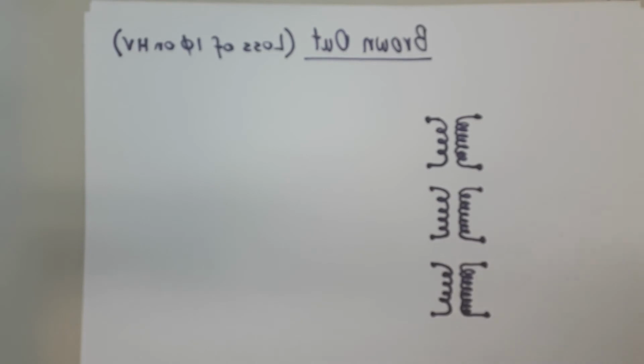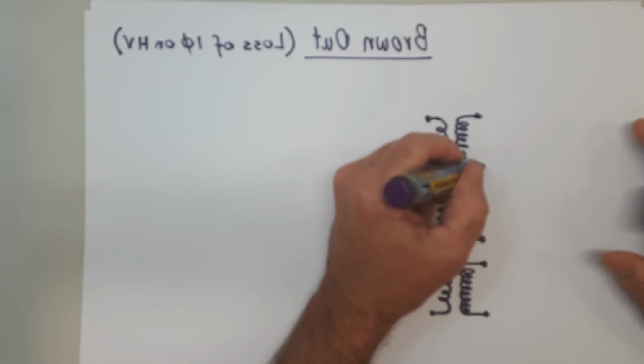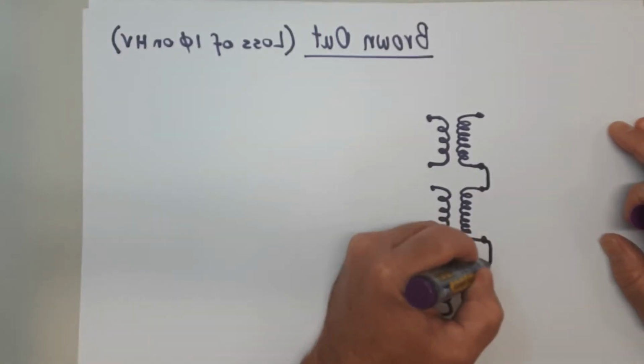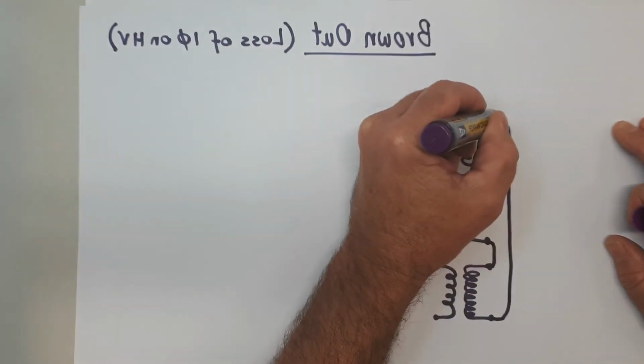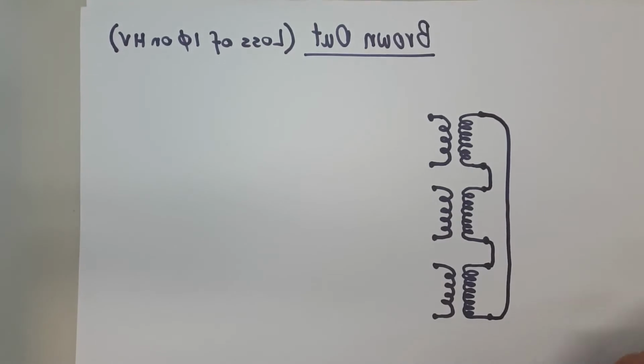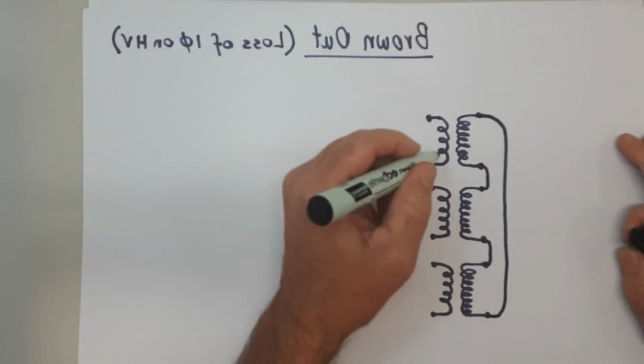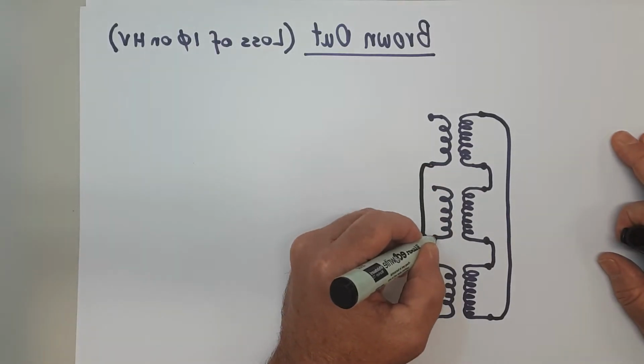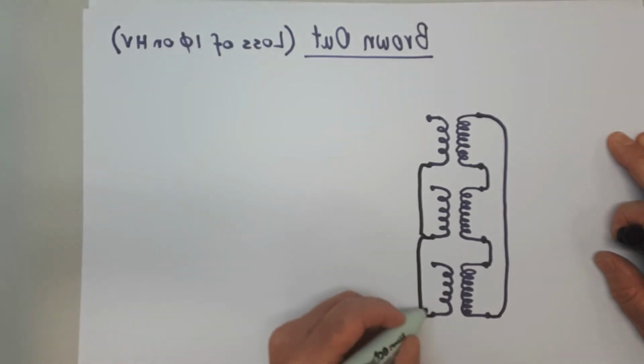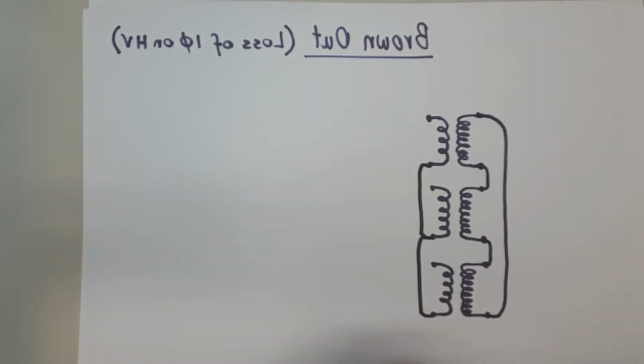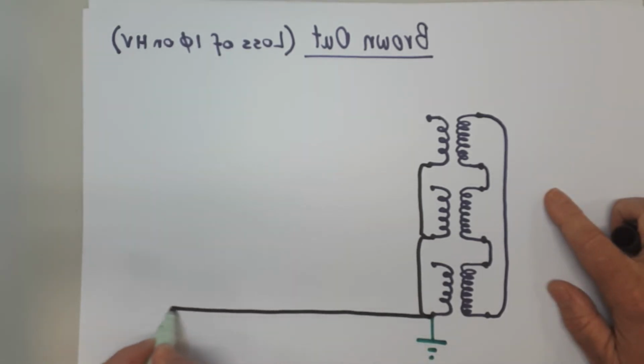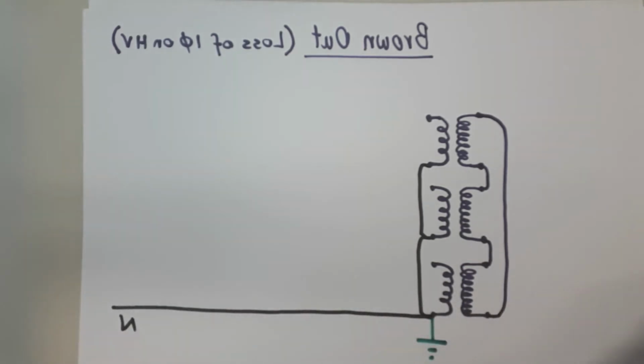what I'm talking about. All right, so if we lose one phase on the high voltage, well, let's connect them all up in delta first and star. So the delta, as we said, is going to be connected in a circle. Join them all up together. So there's our high voltage connected in delta. Now our low voltage, we've starred all the 2s. Okay, we've starred the 2s together, and of course we earth that. That's earthed. And that is the neutral, so that goes out as the neutral. Neutral, and our phases go out like this.